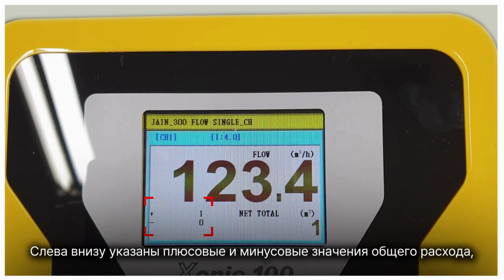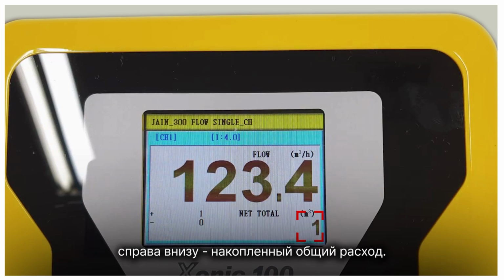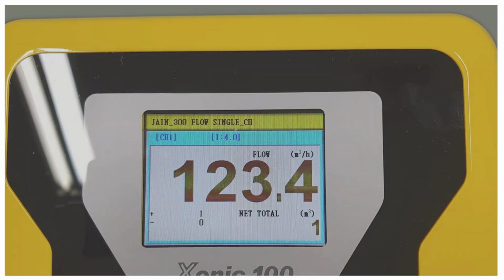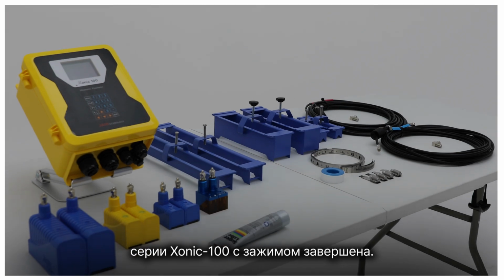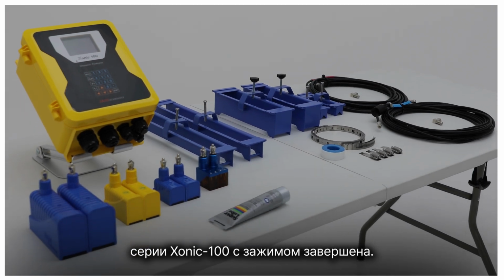The plus and minus values of the total flow are at the bottom left, and the accumulated total flow is at the bottom right. This concludes the installation and settings of the Xonic-100 series clamp-on ultrasonic flow meters.